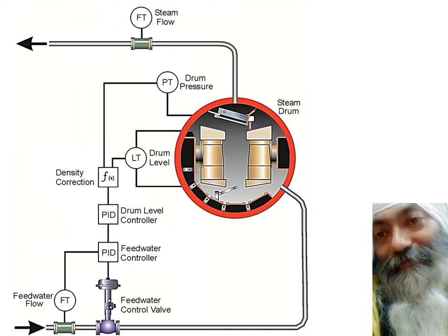So what we see over here is that it is going to take care of two things. First, as it was happening earlier, in case the level is going down, then this PID controller asks this PID controller to increase the flow rate. Earlier this PID controller was directly coupled to this valve. Now it is not directly coupled to it, rather it is giving command to its slave or secondary PID controller to increase the flow rate.